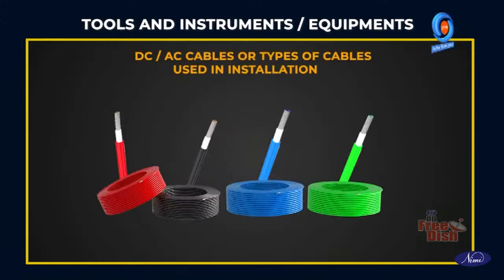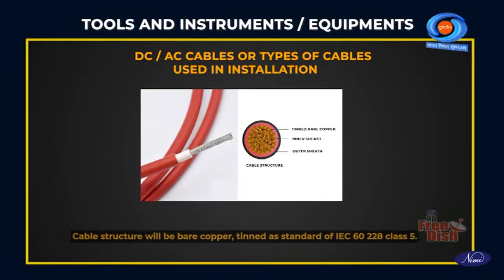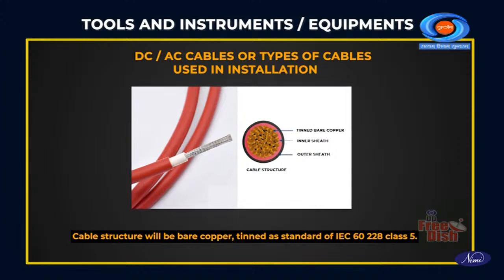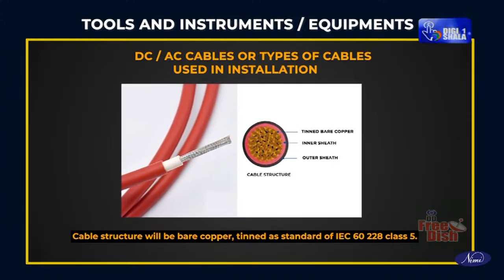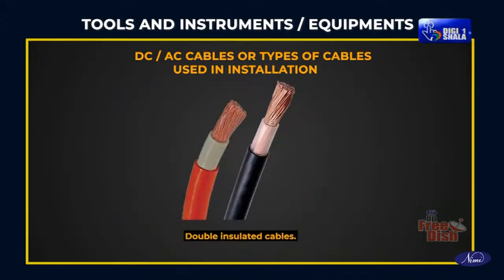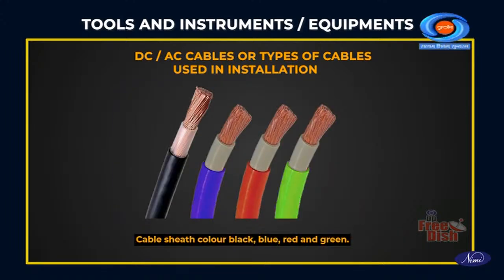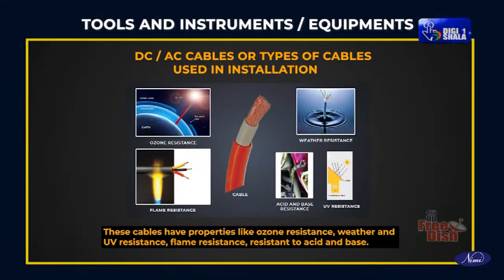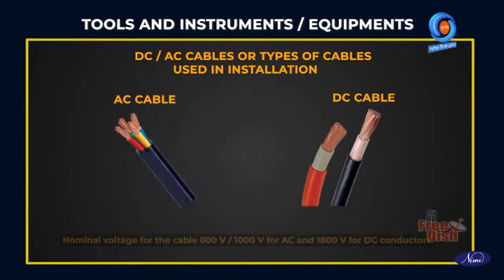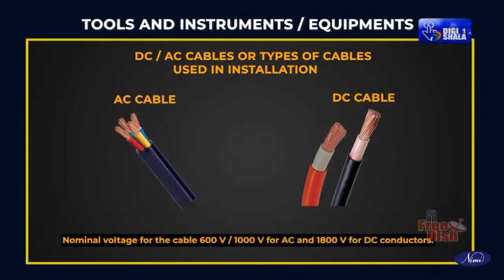Suitable cables: DC or AC cables are the types of cables used in installation. Cable structure will be bare copper, tinned, as per the standards of IEC 60228 Class 5. Double insulated cables. Cable sheath color: black, blue, red and green. These cables have properties like ozone resistance, weather and UV resistance, flame resistance, resistance to acid and base. Nominal voltage for the cables: 600 volts or 1000 volts for AC and 1800 volts for DC conductors.